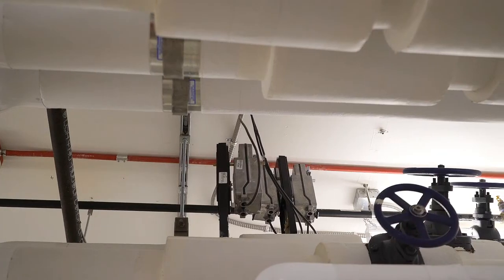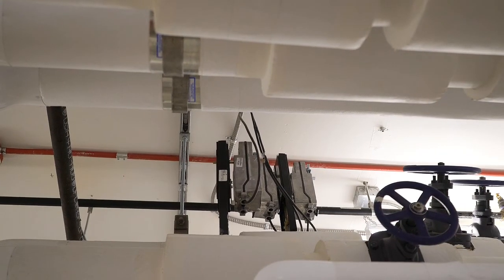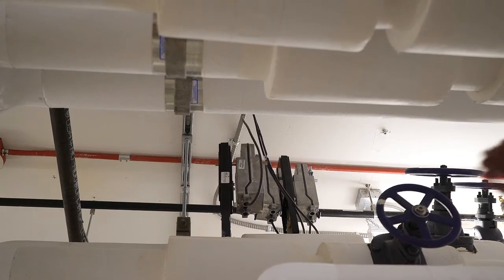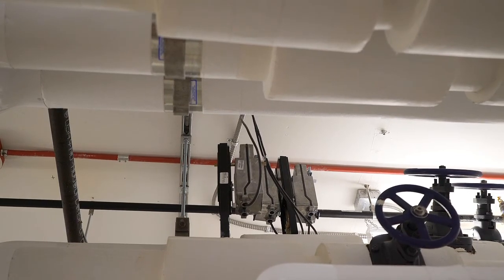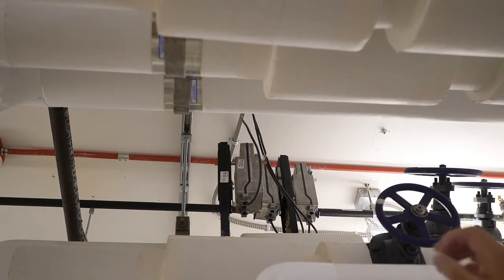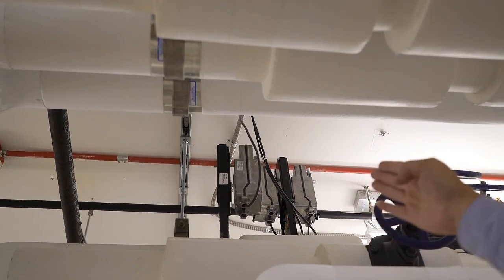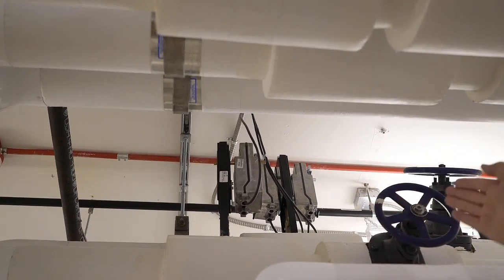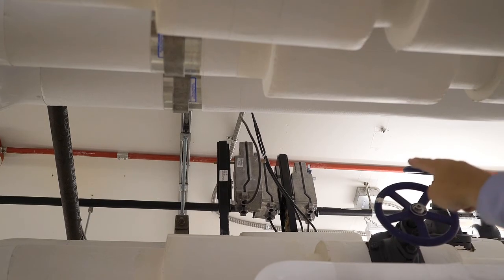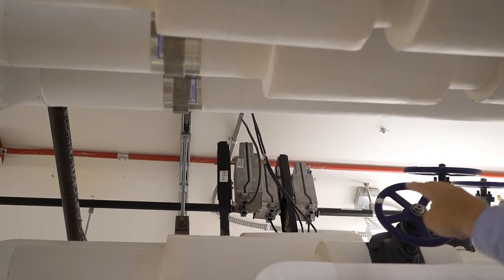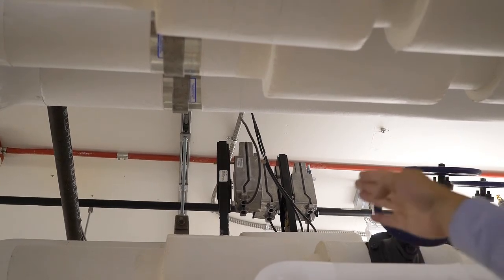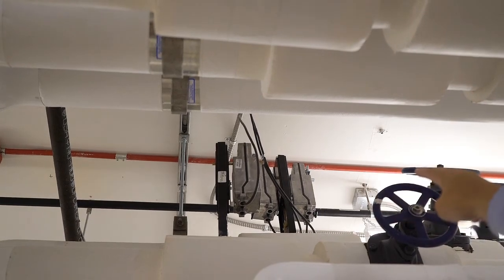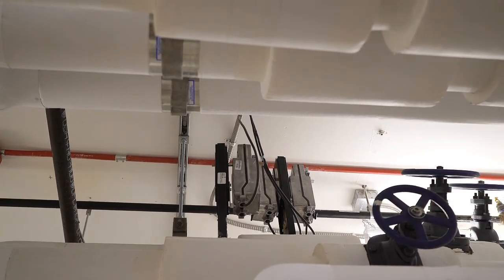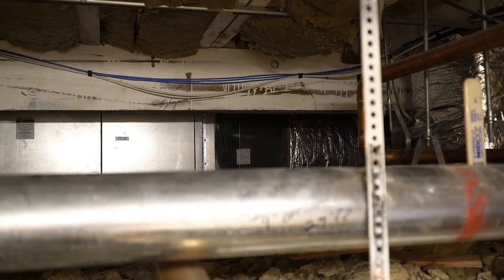So there was a question brought up on the steam valves, how to differentiate between the 1/3 and the 2/3 valves. The 1/3 valve is the smaller valve, so that's the one that has a single actuator on it. The 2/3 valve is a bigger valve, so that's the one that has the double actuator on it to move the stem on the valve. So 1/3 has 1 actuator, 2/3 has 2. And that'll be typical of both heat exchangers.